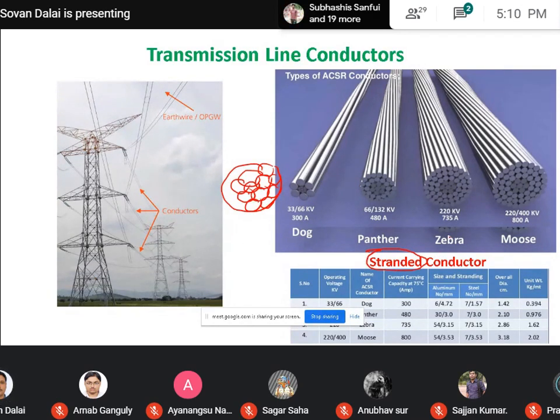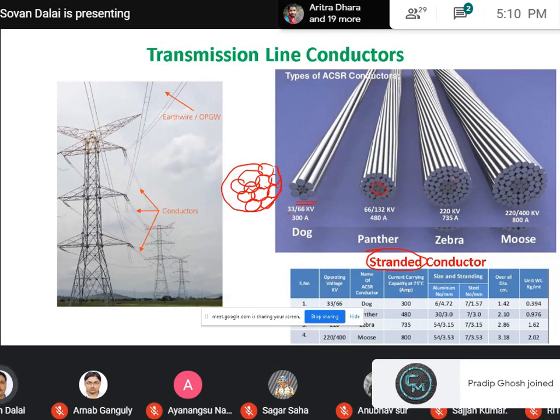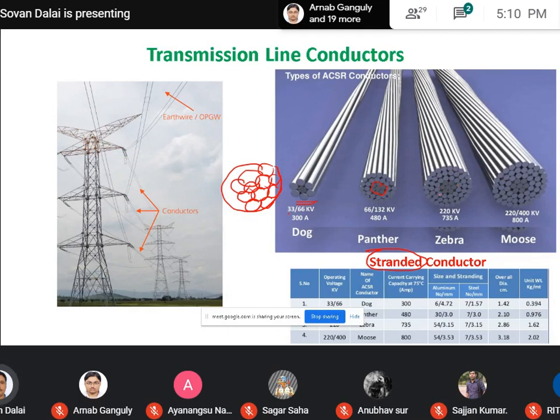Okay. According to the number of subconductors present inside the solid conductor, that is basically decided by the voltage level. So here you see the number of conductors present, say 7: 1, 2, 3, 4, 5, 6, 7 inside this portion. The outer side is aluminium, and the inner side is the steel conductor.